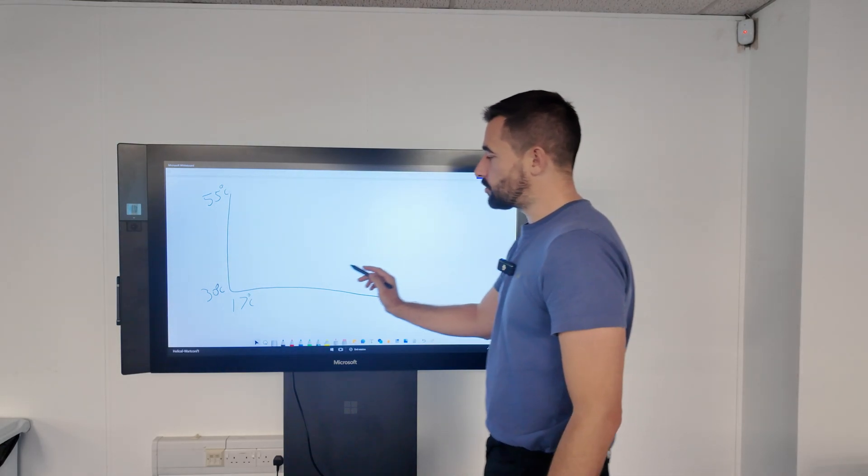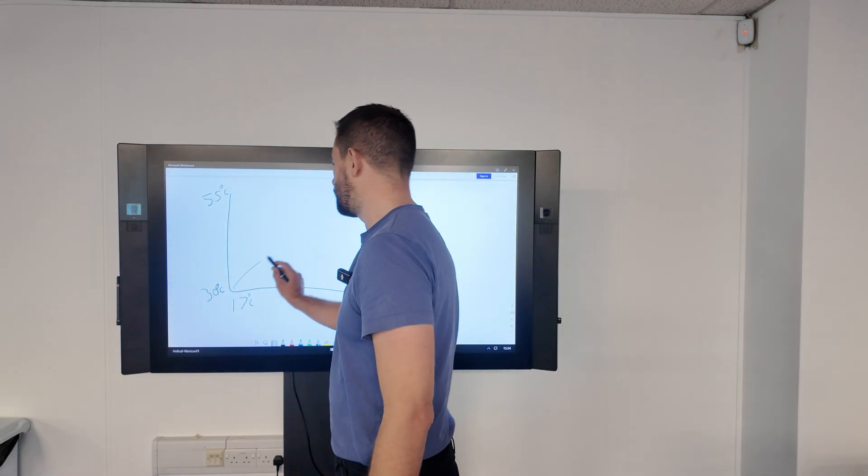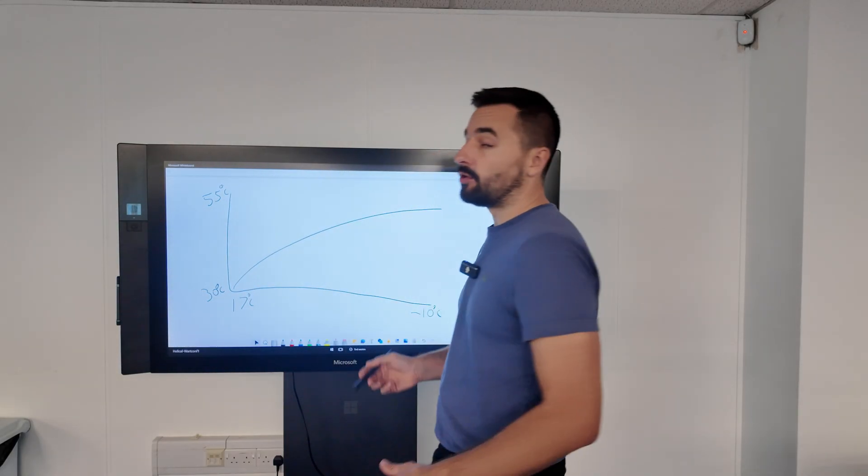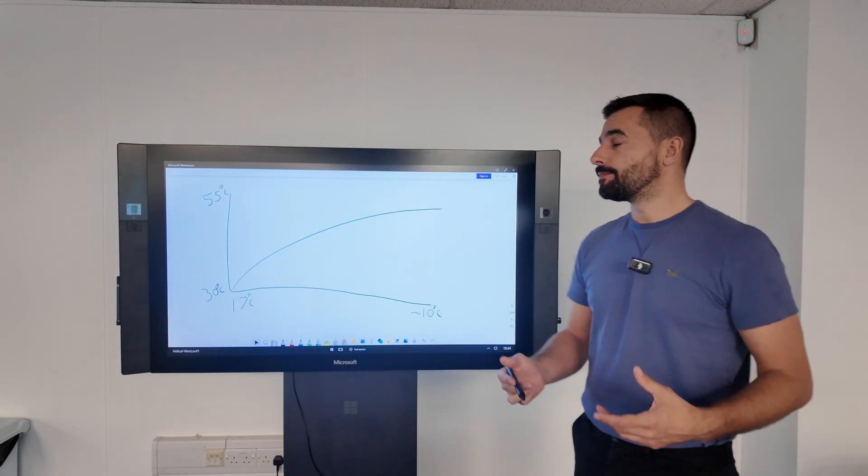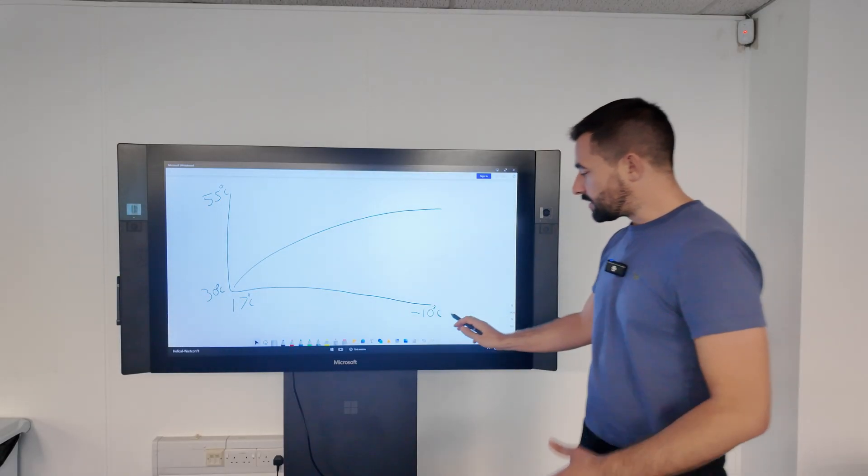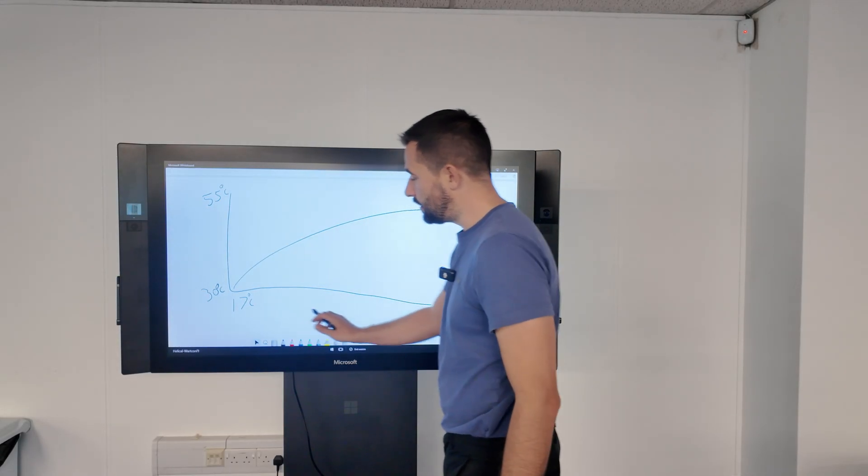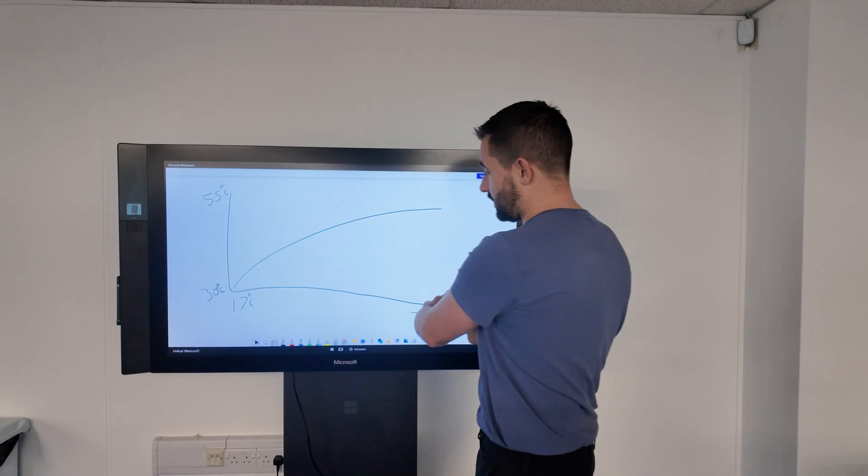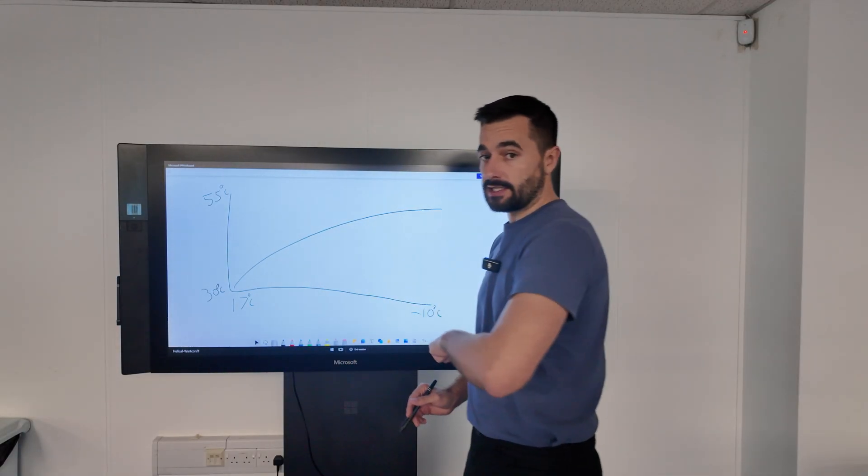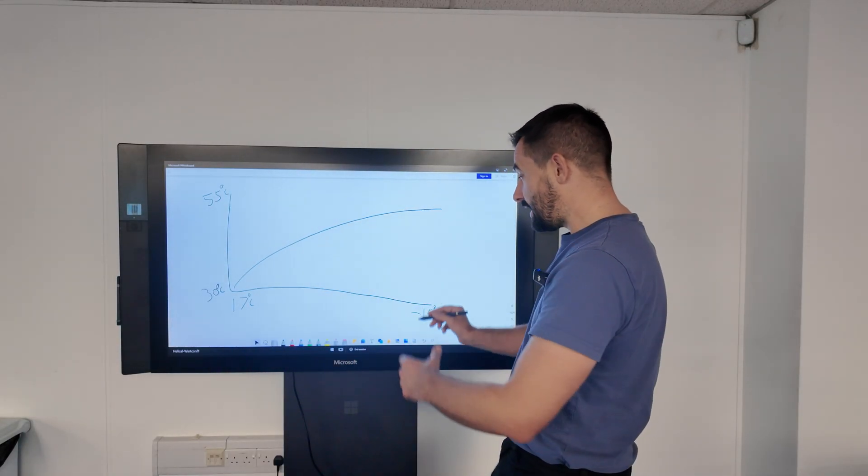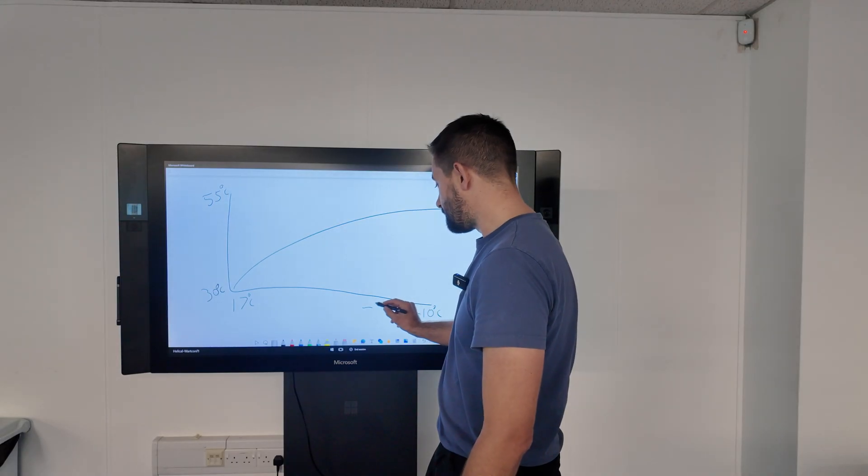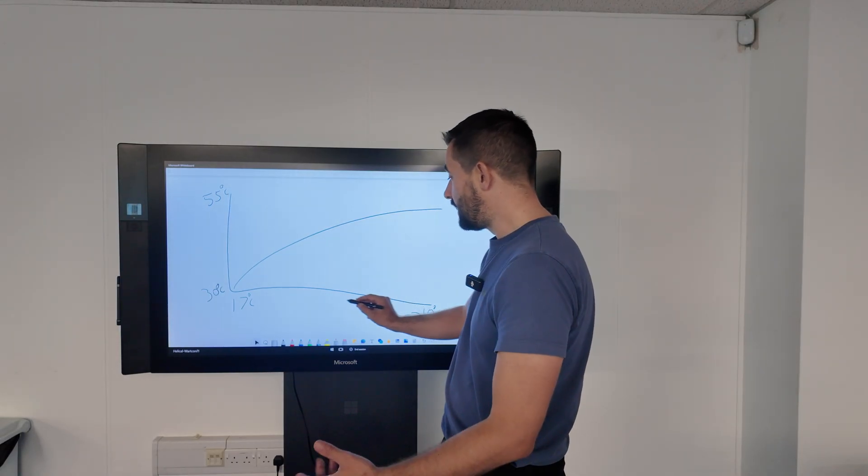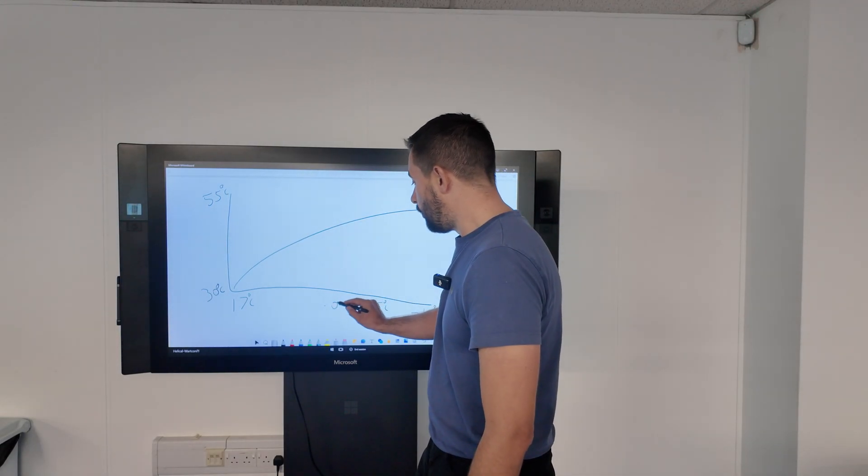On this graph I'm going to plot a curve, which is what we call a weather compensation curve. What the controller is doing is looking at this information here, the outdoor temperature. It's ranging here from minus 10 to plus 17 degrees Celsius. If we take our design temperature which was minus 5 and put it there, imagine we've got all the other temperatures in the range plotted in between.